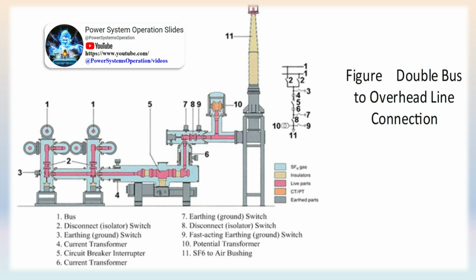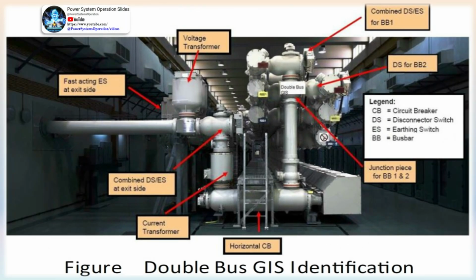Gas-tight modular design. Each compartment housing the live sections of the GIS system is gas-tight with respect to one another. This ensures that the gas is not allowed to pass to an adjacent module, as well as ensures that gas monitoring is independent. O-rings are installed at the equipment and enclosure flanges to ensure the gas-tight integrity of the modules.